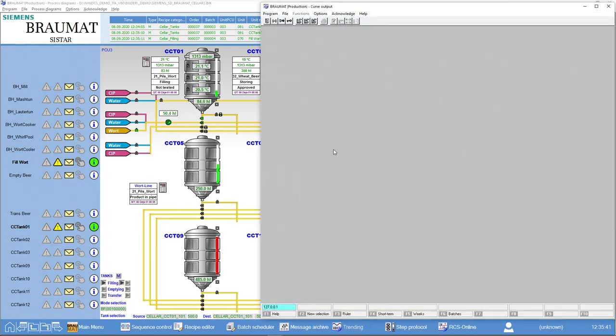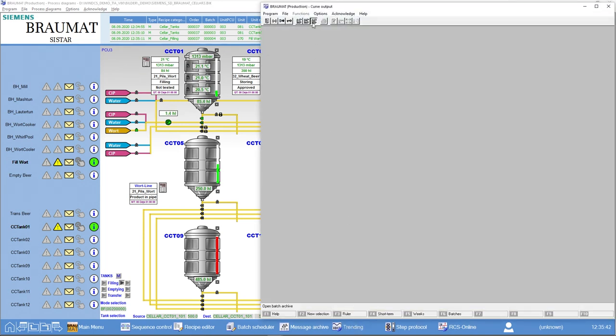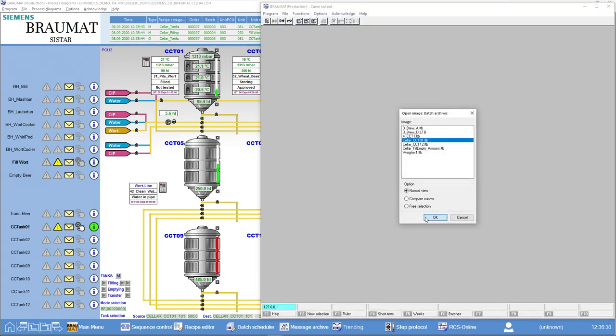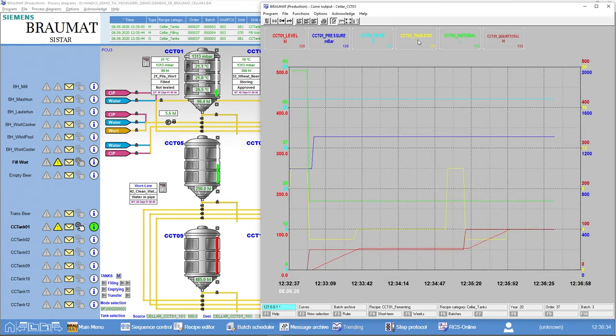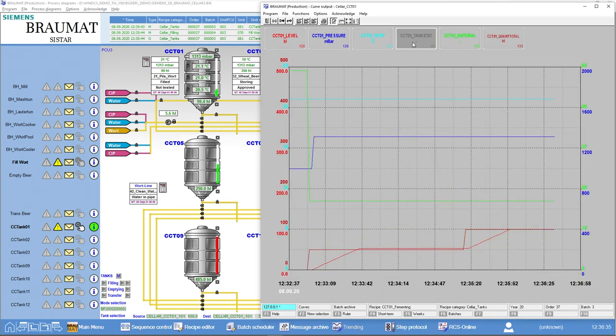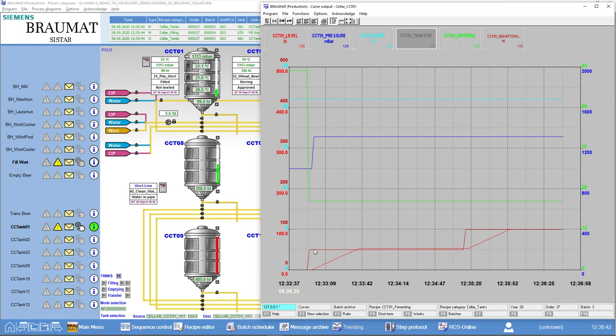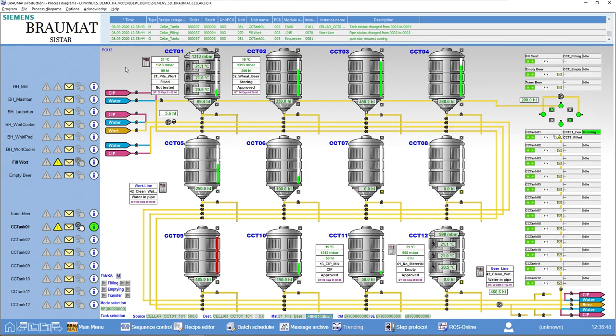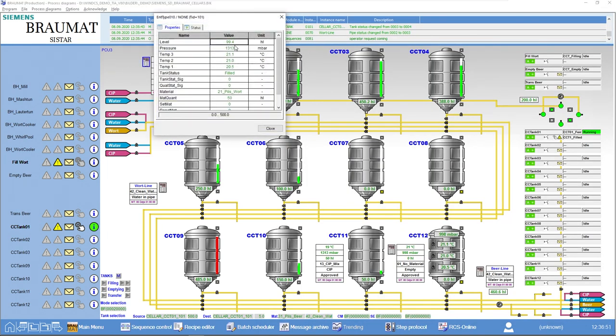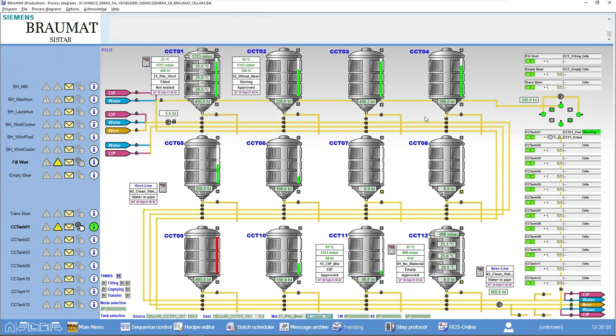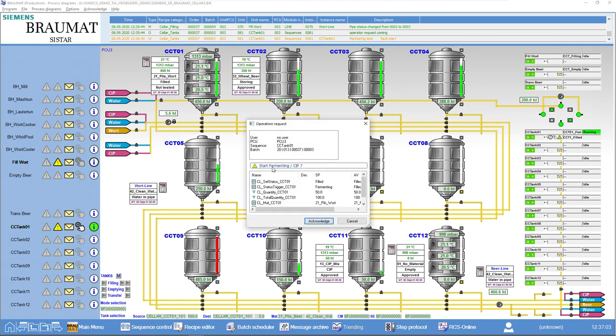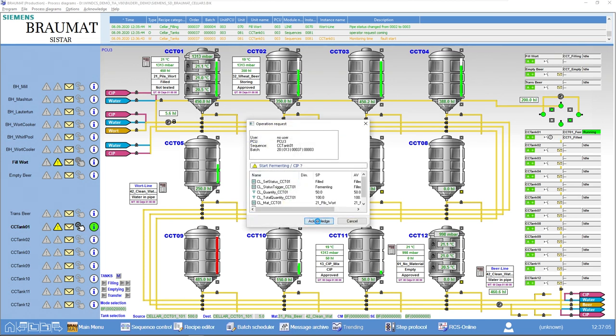Okay, so we can take a look at the whole thing again in trend. Here is tank number 1, with the current batch. I am going to hide a couple of things that we don't need. This red line is the filling level in the tank. This dark red is the book value. And up here, we have pressure and temperature. I want to speed the whole thing up now. So let's imagine the tank is now full. I switch this operator request to start fermenting. Then, as you can see, the corresponding cooling zones are activated. The relevant valves are opened. The temperature decreases. And we find ourselves in the logistically independent step of fermenting.